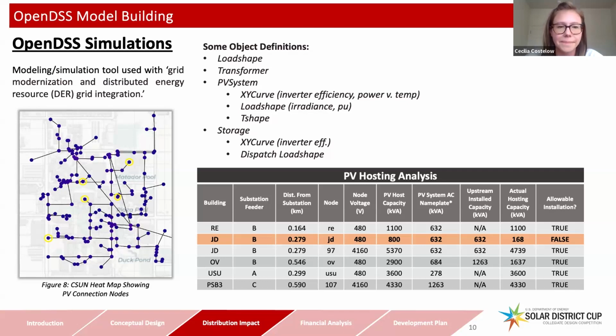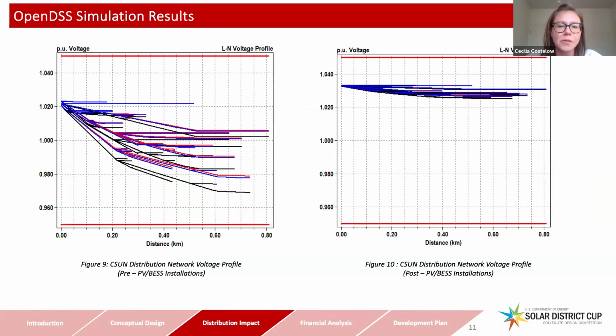Next slide, please. So these are some of the results from our OpenDSS simulations. The image on the left shows what the CSUN distribution network voltage profile was before we installed any PV or battery. You can see it's nicely centered around 1 PU, as would be expected. After we've installed all of our PV and BESS installations, the voltage profile of the entire system is lifted, which is also as expected, but you can see we're still within plus or minus 5% of 1 PU as required.